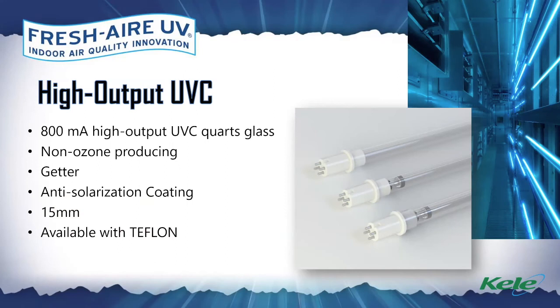But what's so unique about the Fresh-Aire UV quartz glass lamps is that they are high output. There's standard output lamps at 400 milliamps. These are high output UVC lamps at 800 milliamps. They do not produce ozone. They're doped. There's an internal doping of the glass that allows the UVC light at 254 nanometer to be produced, but it will not allow the light to drop down at the 185 that would produce ozone. So these are non-ozone producing.